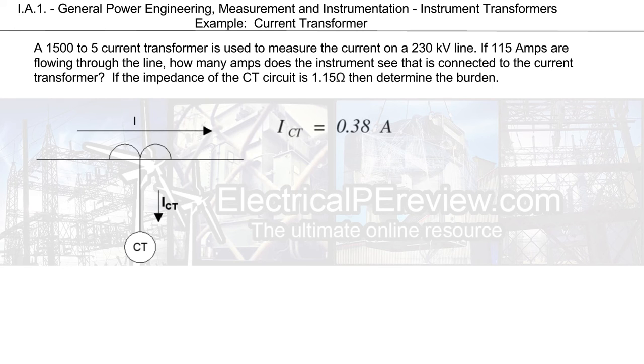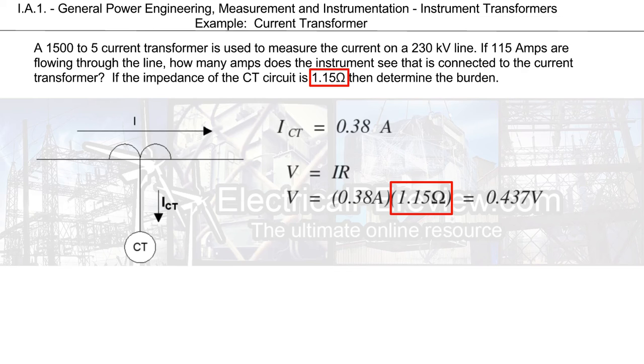Okay, now that we've got our CT amps, we're going to use this information to find the burden. Using standard Ohm's law, we can calculate the voltage seen at our CT as 0.437 volts. Our Ohms here is given to us in the problem statement as the impedance of the CT circuit itself.